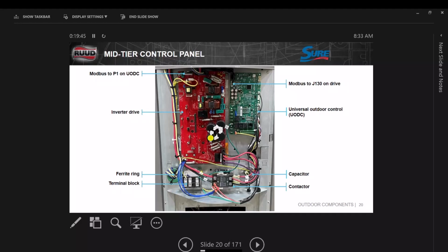We have our terminal block down here. Redesigned that, put it on a metal bracket there. Right here at the top, you'll see that Modbus, that J130. That is a jumper that goes from this board on the right side over to the inverter board. Brings communications back and forth to the 2 boards. Okay.